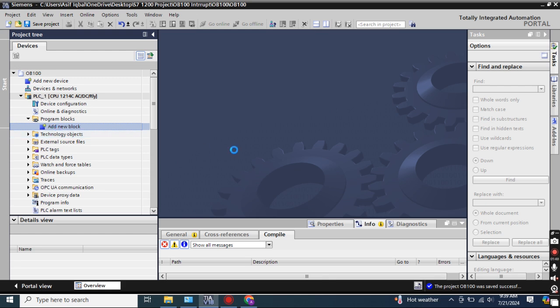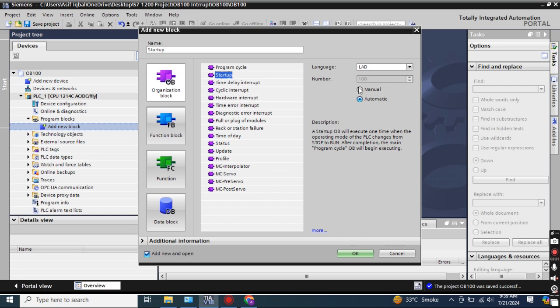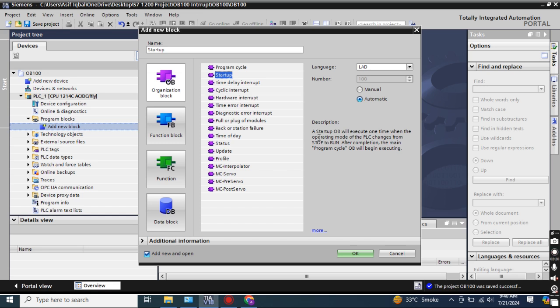To add OB-100 in TIA Portal, click 'Add new block' and select the organization block — this is OB-100 Startup. One important thing: this organization block only runs once, not like other cyclic interrupts that keep running on different cycles. It only runs when the CPU starts. The language is Ladder, the number is 100 for OB-100.